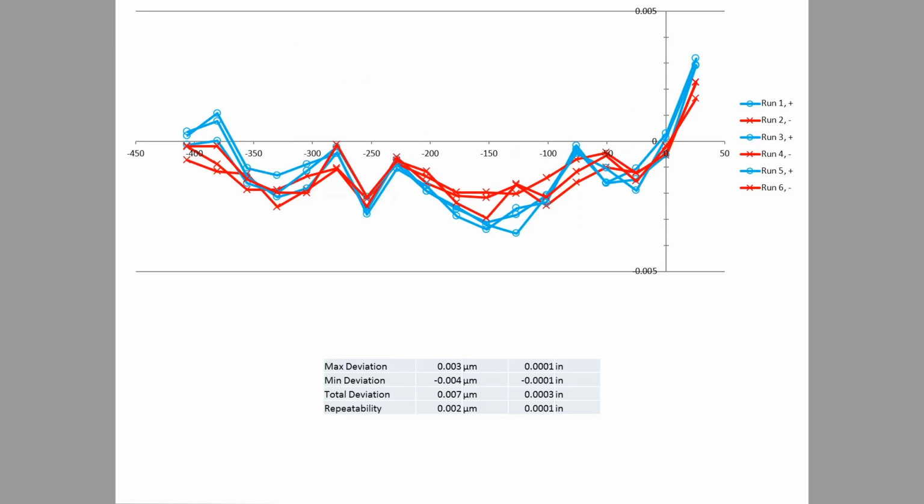The reason is we didn't pick these numbers out of a hat. We came up with these by measuring during the compensation run. Both these points are generally within the repeatability of our compensation run. We shouldn't expect much more out of correction by the control. Now, let's say, for example, we did change the compensation value at minus 150 millimeter and add a little bit so it'd get closer to 0.